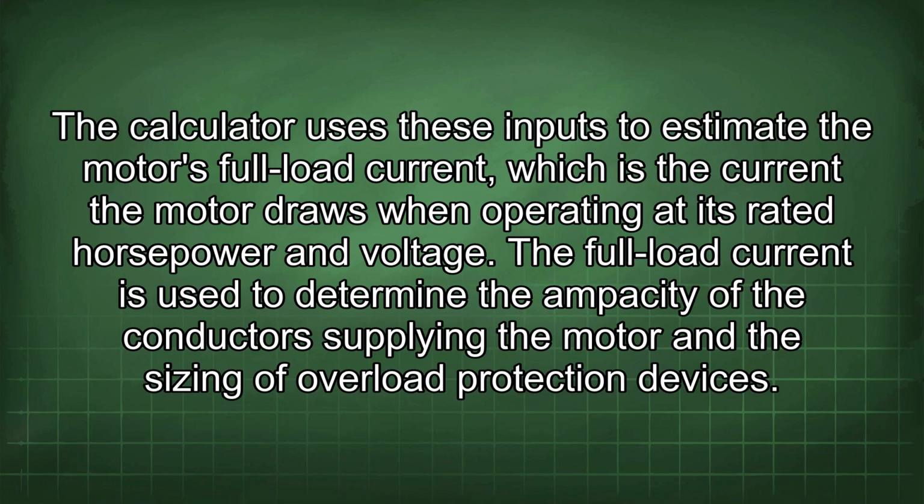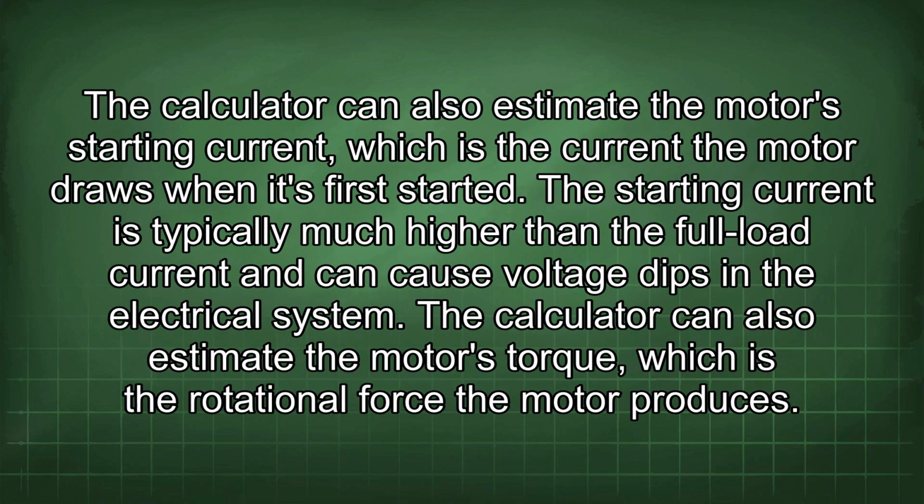The calculator uses these inputs to estimate the motor's full load current, which is the current the motor draws when operating at its rated horsepower and voltage. The full load current is used to determine the ampacity of the conductors supplying the motor and the sizing of overload protection devices.